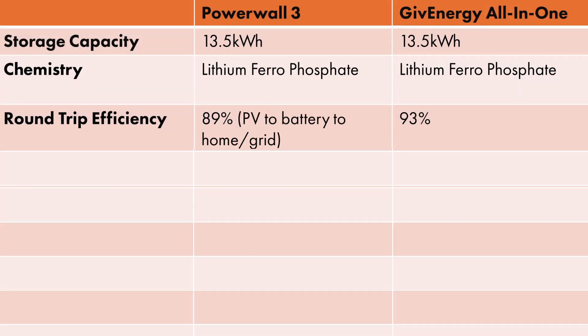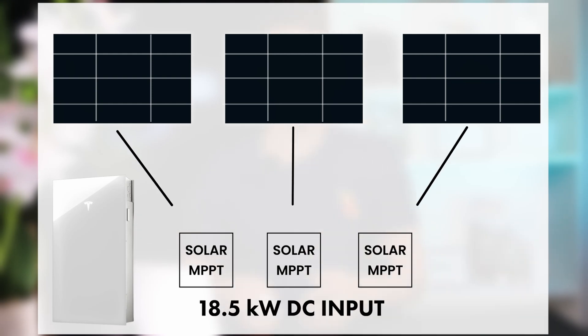What about the inverter functionality? The two are very different and have different use cases. GivEnergy's is a 6 kW AC coupled inverter, whereas the Powerwall 3 inverter is DC coupled and can be set to anywhere between 3.68 kW and 11.04 kW. Powerwall 3 also has three solar MPPTs, which can handle three different solar arrays and over 18.5 kW of DC input, which makes it the best single phase solar inverter on the market today.